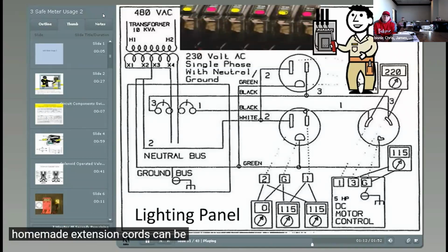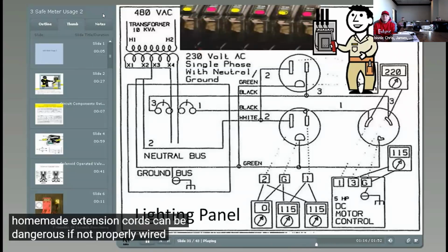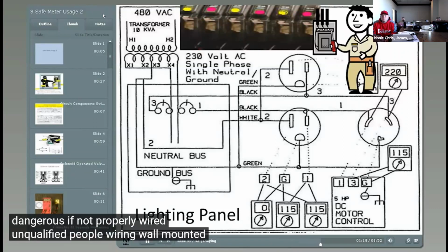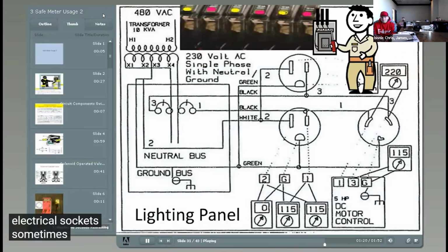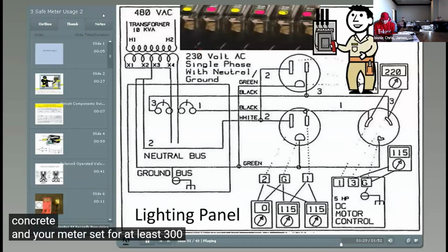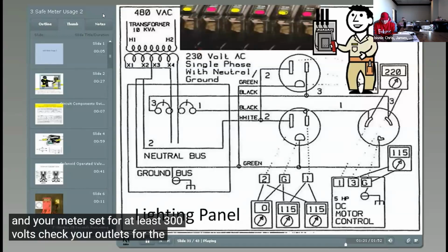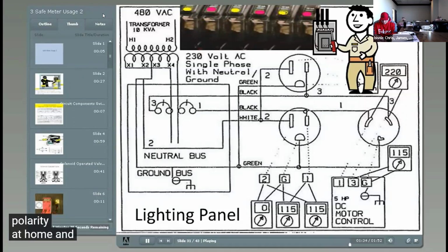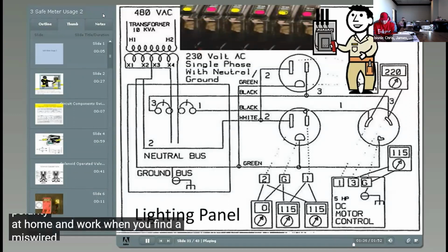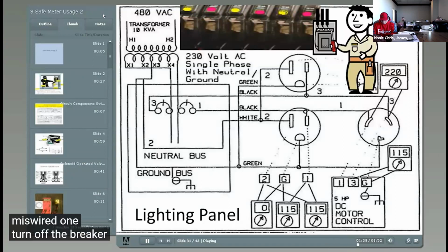Homemade extension cords can be dangerous if not properly wired. Unqualified people wiring wall-mounted electrical sockets sometimes get it wrong. With your safety glasses on, and you not standing with wet feet on concrete, and your meter set for at least 300 volts, check your outlets for the proper polarity at home and work. When you find a miswired one, turn off the breaker after verifying your meter works, and rewire properly after verifying the power was truly disconnected.